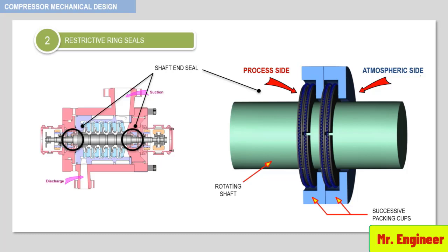The shaft packing is always of the floating type and consists of several annular packing cups and segmental packing rings. In this example, you can see two packing cups and four packing rings. This arrangement is held inside the compressor as a complete assembly, using the appropriate studs and nuts that secure the assembly against a sealing gasket.